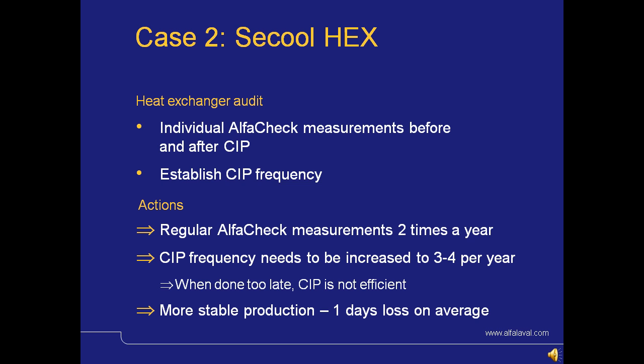The fact is that the process conditions change all the time. It can be everything from the process flow increasing or decreasing. It can be from the quality of the product changing. It can be the temperature of the cooling water going up or down, seasonal changes or yearly changes. This means that you need to check the performance regularly, even though you think that you know when to clean.